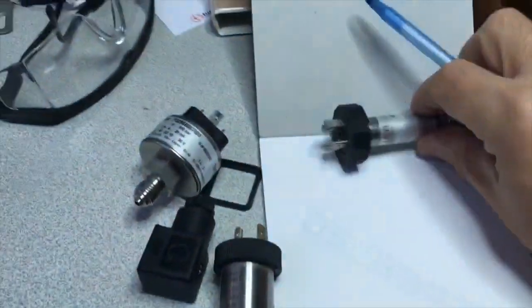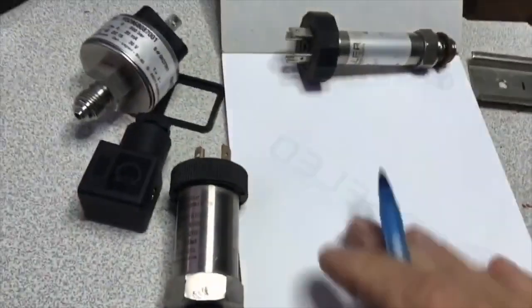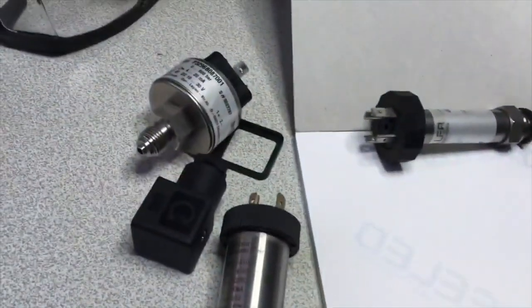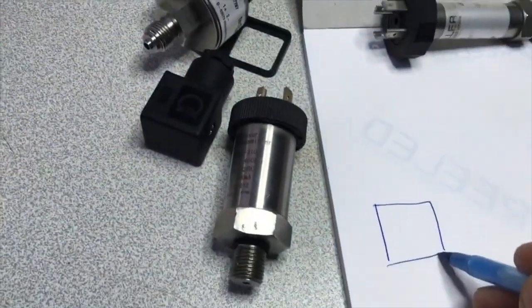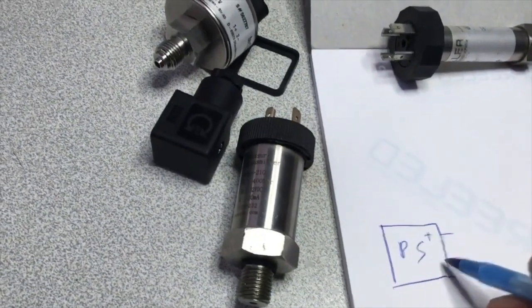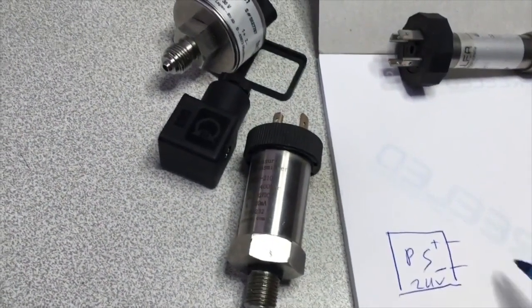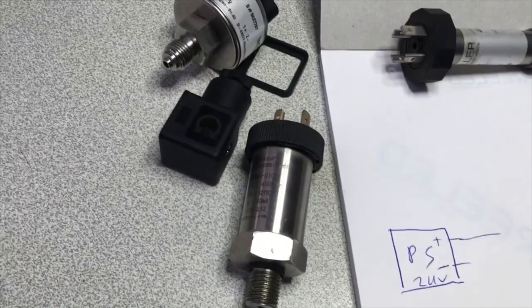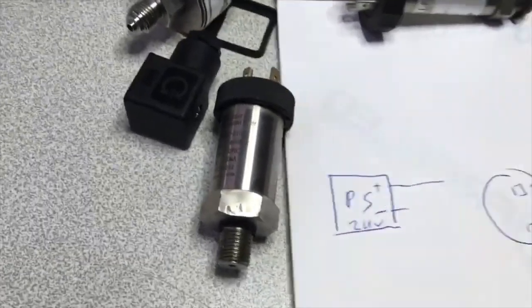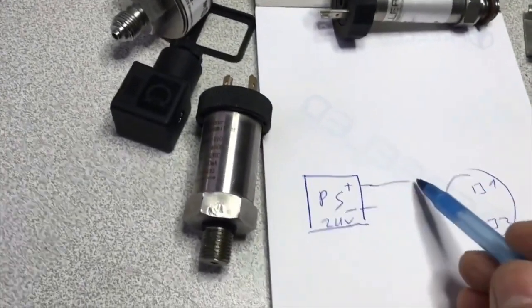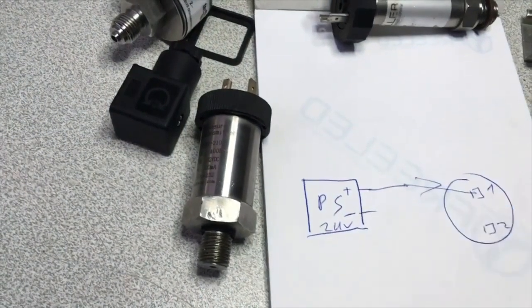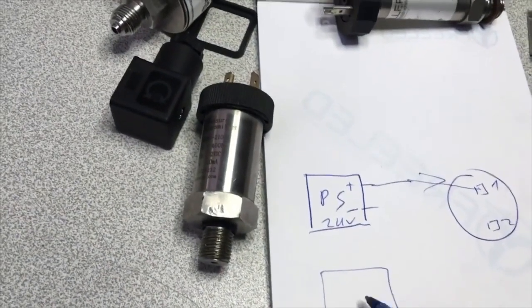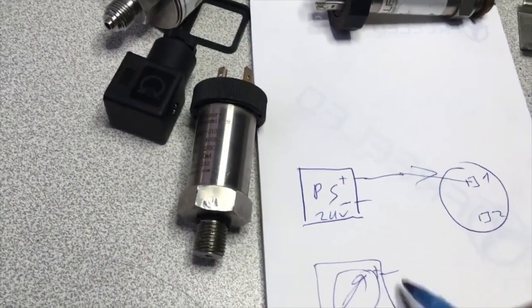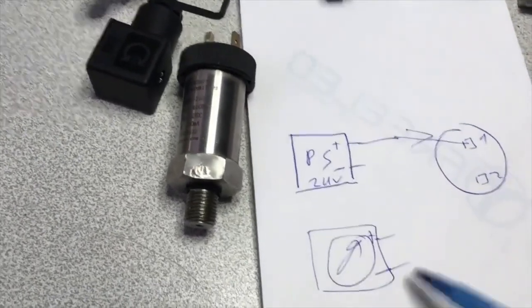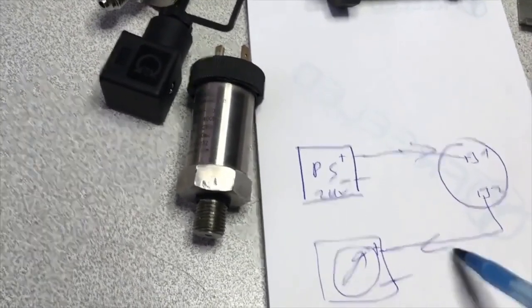Usually, when we buy such sensors, a paper comes out of it. The connections are described here, but the connection principle of the current outputs is generally the same, just look at the numbers. Let's call it 24 volts DC. Let's draw the sensor here, whether it's number 1 or number 2. The connector is usually connected to 2 of them. We go to number 1 like this. Let's put the plus of 24 volts here, or if you want, put our milliamperemeter here, whether it's plus and minus. This controller can also be the analog input of the PLC from number 2.